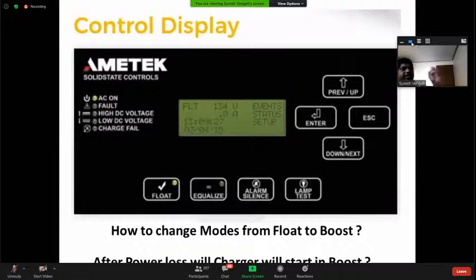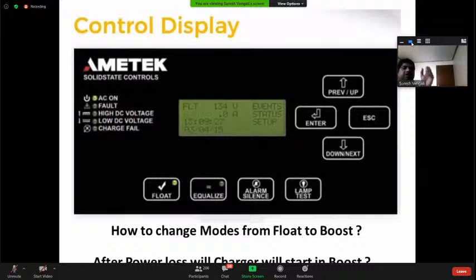So on the same screen you can simply change it to float or equalize mode, just keep in mind that after power loss, the machine will think: I lost power, my battery is depleted 30-40%, so I need to charge back. If you have an auto feature inside, automatically after power loss and power return, it will shift back to equalization mode.